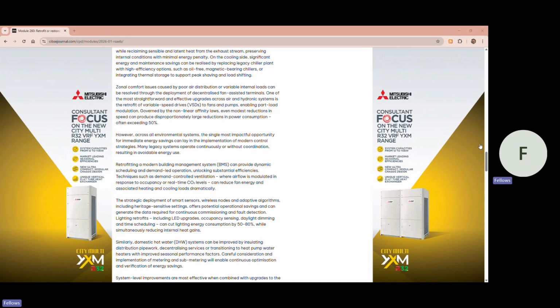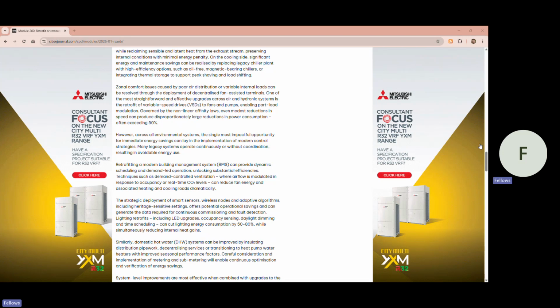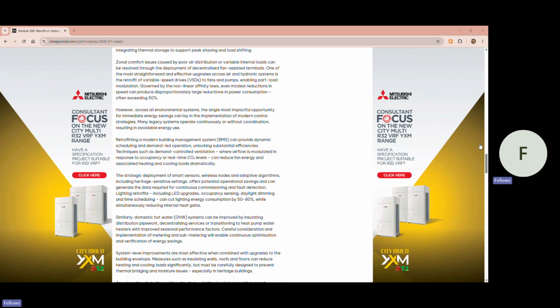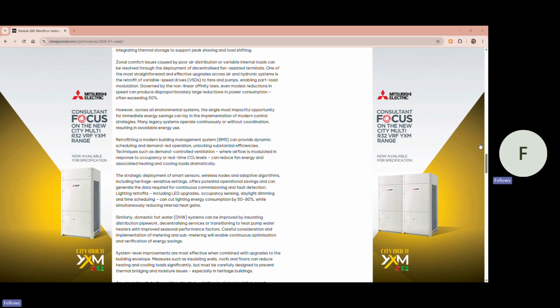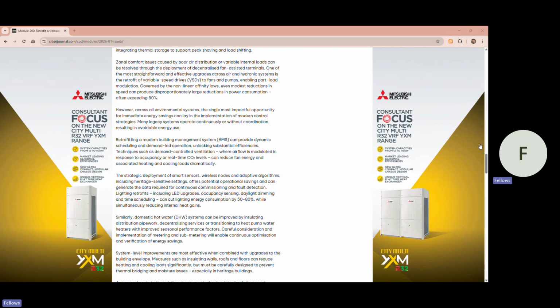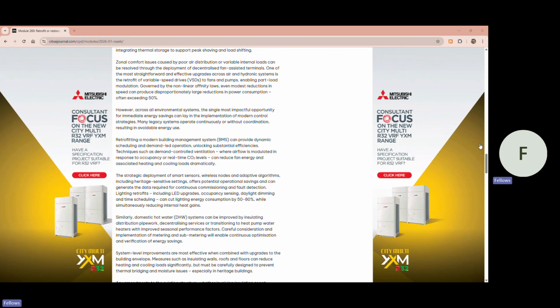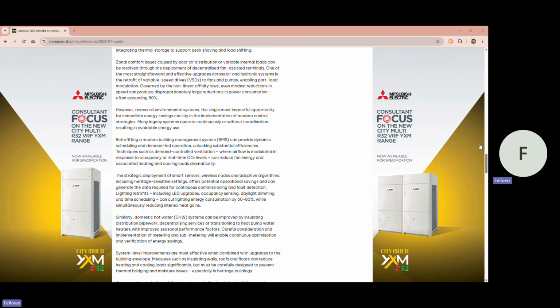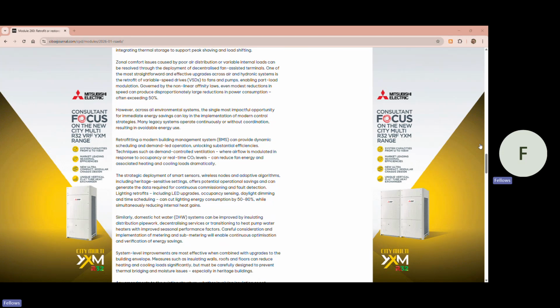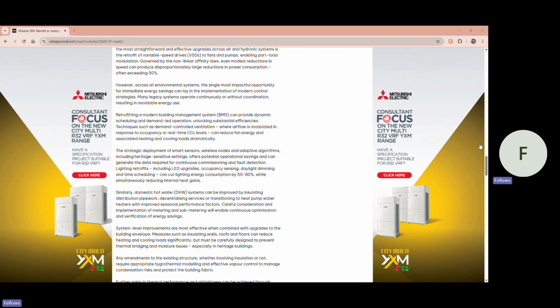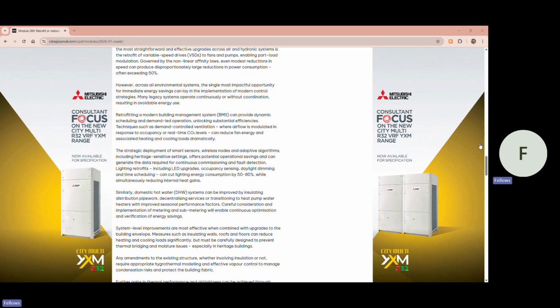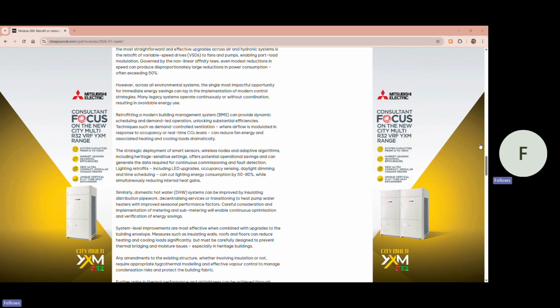Many legacy systems operate continuously or without coordination, resulting in avoidable energy use. Retrofitting a modern building management system, BMS, can provide dynamic scheduling and demand-led operation, unlocking substantial efficiencies. Techniques such as demand-controlled ventilation, where airflow is modulated in response to occupancy or real-time CO2 levels, can reduce fan energy and associated heating and cooling loads dramatically. The strategic deployment of smart sensors, wireless nodes, and adaptive algorithms, including in heritage-sensitive settings, offers potential operational savings and can generate the data required for continuous commissioning and fault detection.